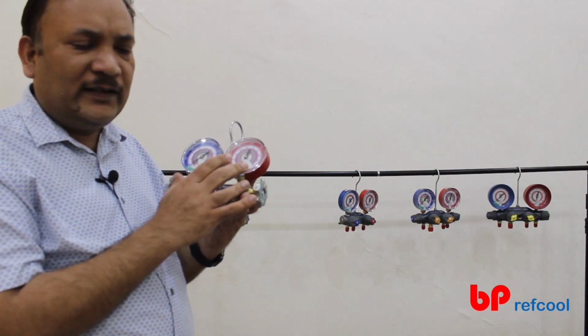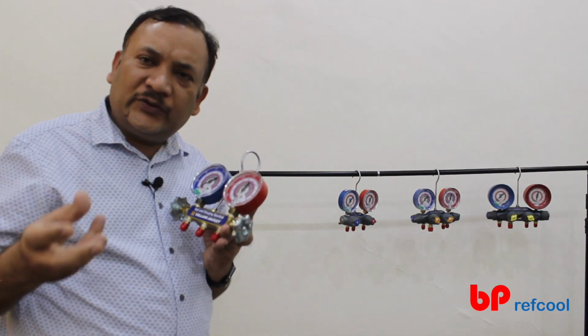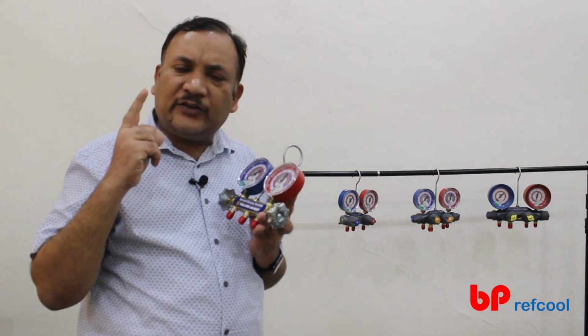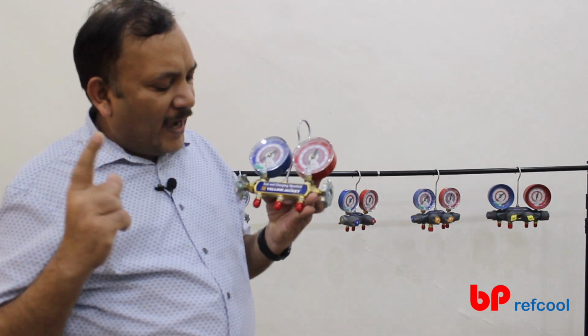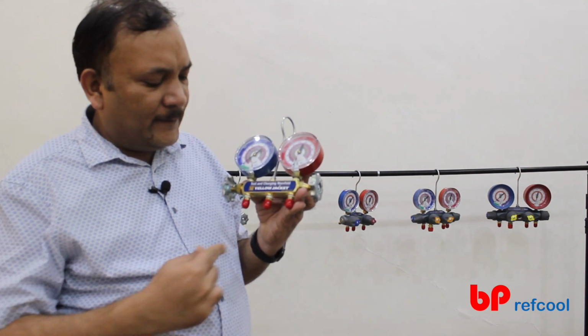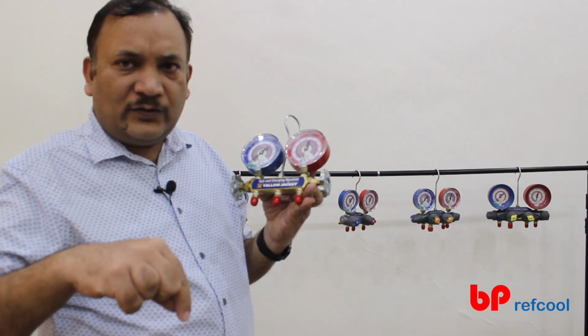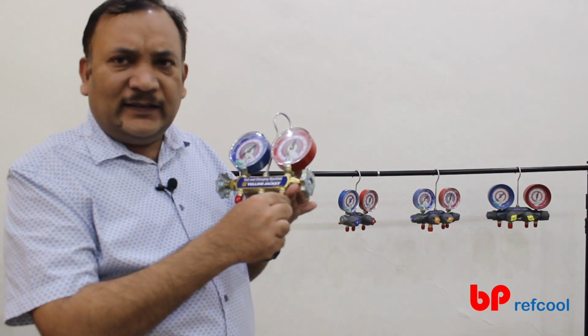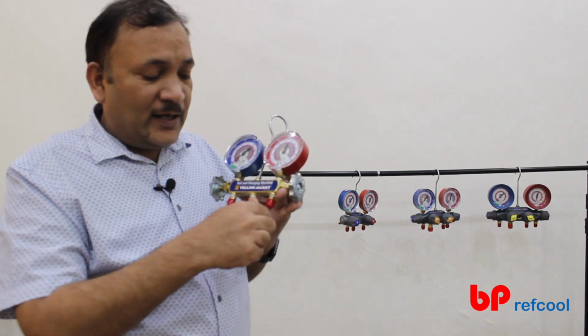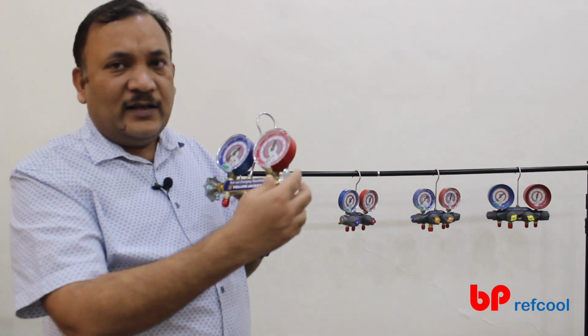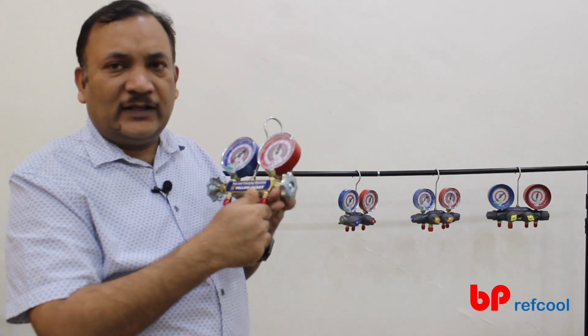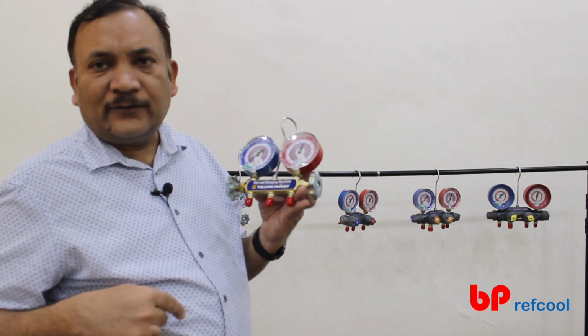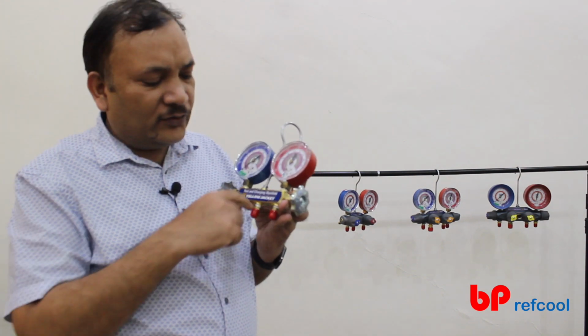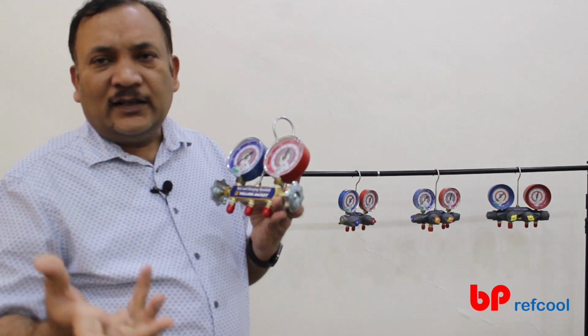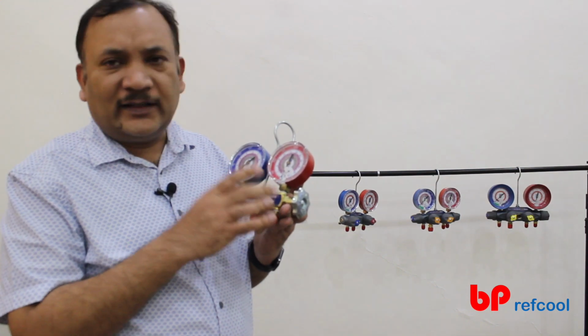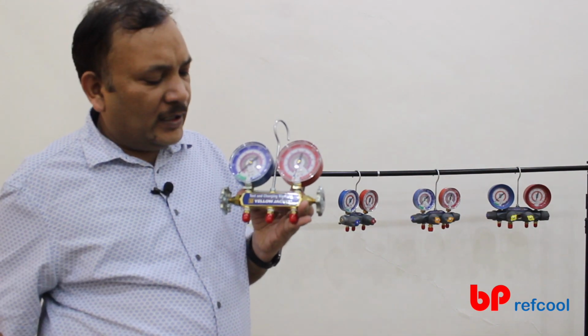A lot of people use this even for a refrigerator or a room air conditioner where there is only one port available. So in that case what they do is when they are doing the vacuuming, they connect this line to the vacuum pump, this to the system, and this they connect the vacuum gauge. Once they connect the vacuum gauge, they can read, and after doing the vacuum they just close this, remove the vacuum gauge and do the gas charging from this port. So they essentially use this as a T in that case. But yes, this is something which is very commonly used.